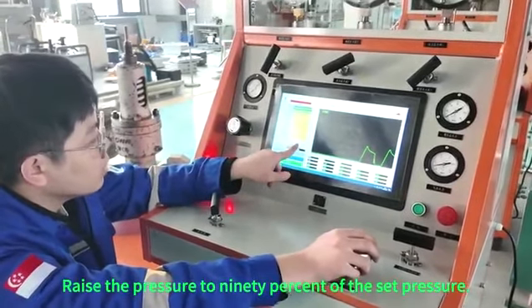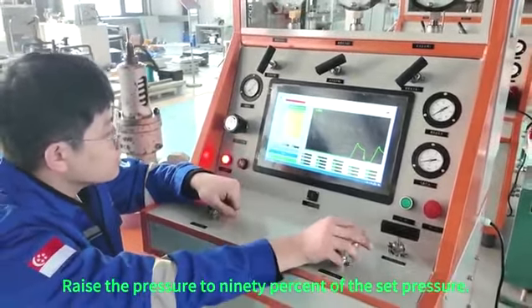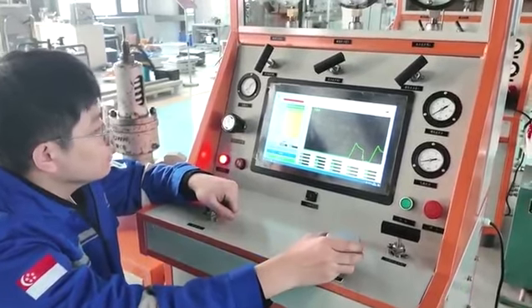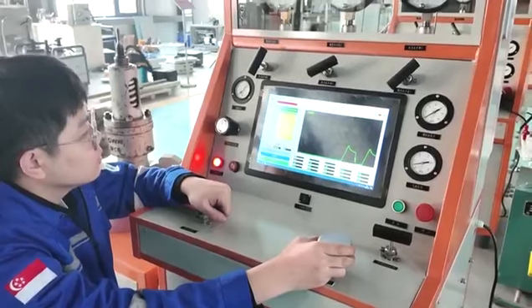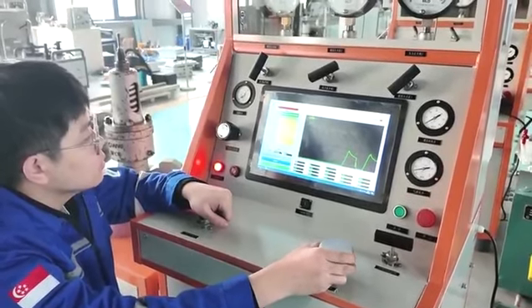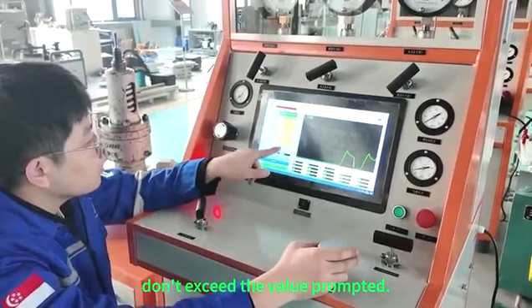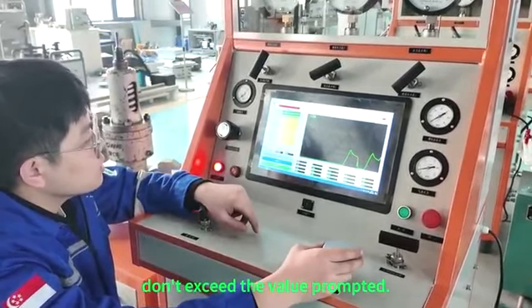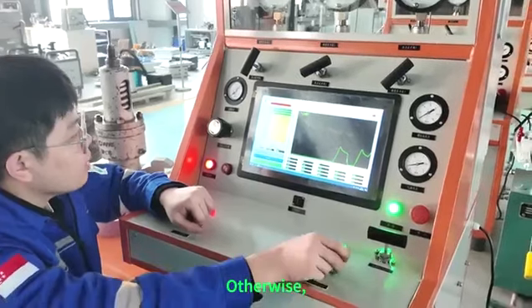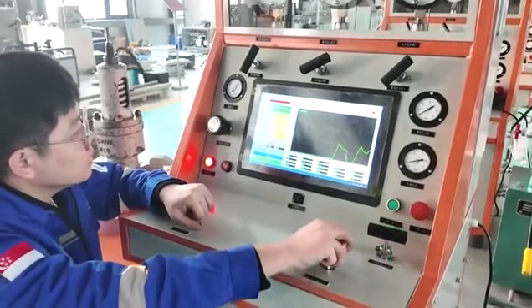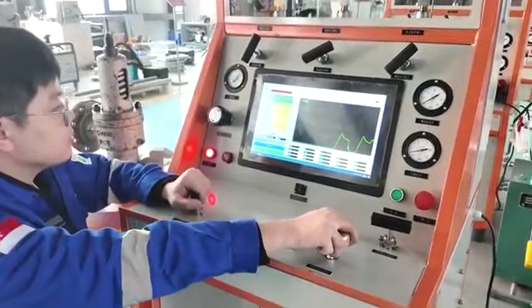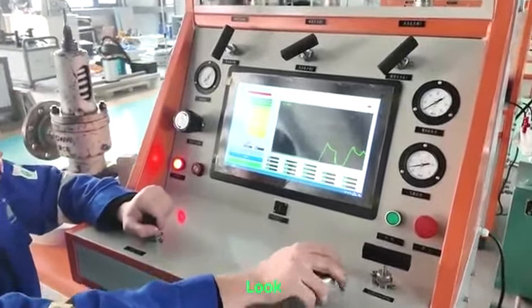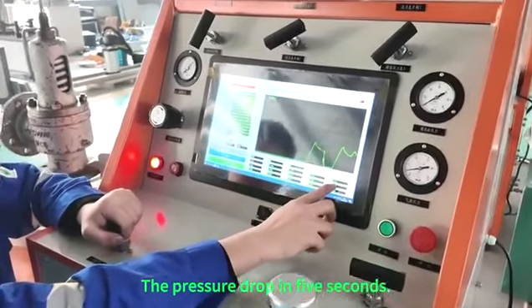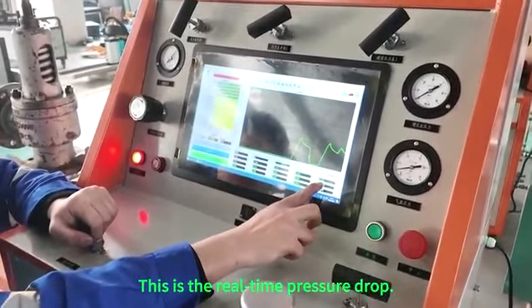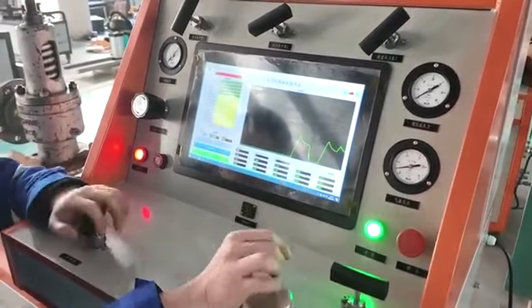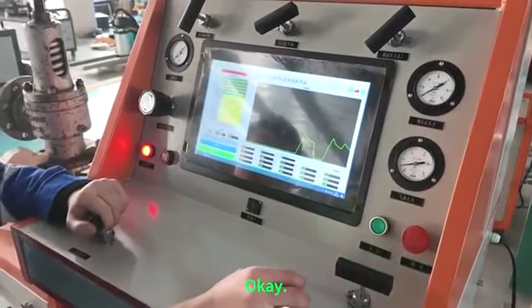Raise the pressure to 90% of the set pressure. When boosting the pressure, don't exceed the value prompted. Otherwise, the seal can't hold the pressure. Look, this is the pressure drop in 5 seconds. This is the real-time pressure drop. Okay.